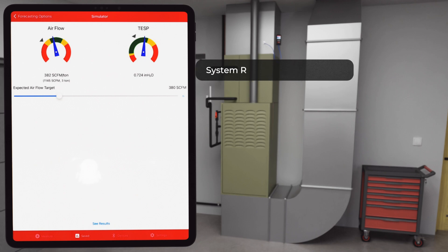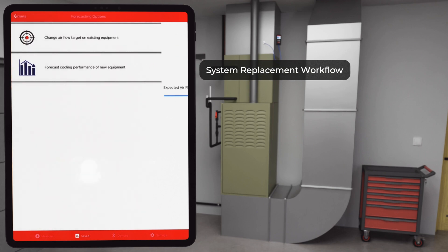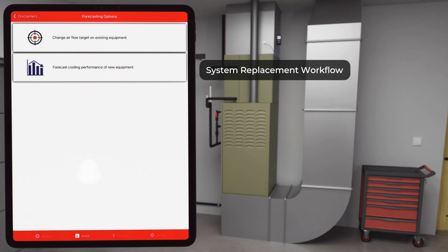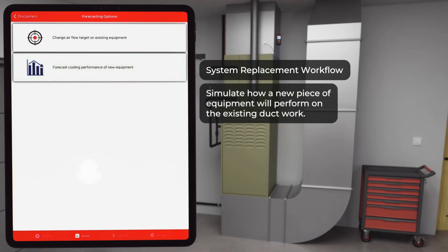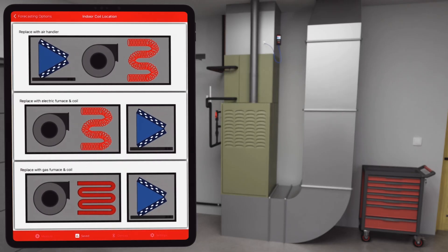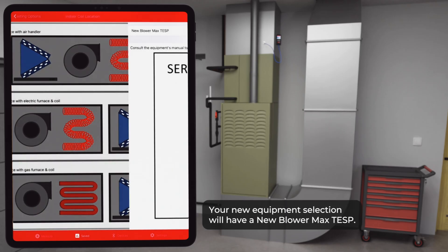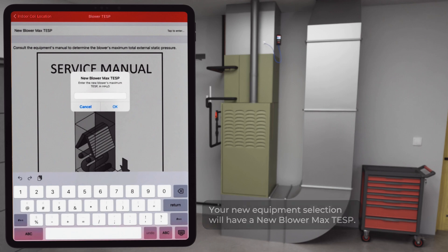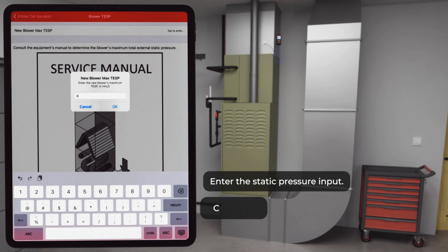Now, time for the system replacement workflow. Starting back at the forecasting options screen, the second forecasting path is system replacement. This allows you to simulate how a new piece of equipment will perform on the existing ductwork. After selecting this mode, you'll choose the type of indoor equipment: air handler with internally mounted coil, electric furnace with externally mounted coil, or gas furnace with externally mounted coil. Your new equipment selection will have a new blower max TESP. Enter this static pressure input and select continue.